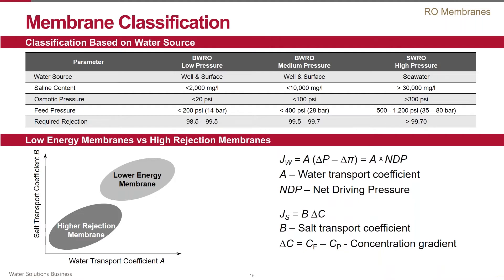Brackish water membranes are designed to treat lower salinity — anything below 10,000 milligrams per liter. Within this classification, there are subsets rated for different performance. For example, within the seawater domain, we can differentiate high rejection and low energy membranes, and the same applies to brackish water membranes. Low energy membranes are designed to reduce the energy required to generate permeate, while high rejection membranes offer better permeate quality at the expense of energy savings.